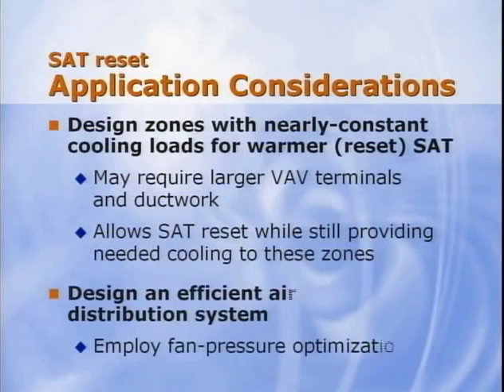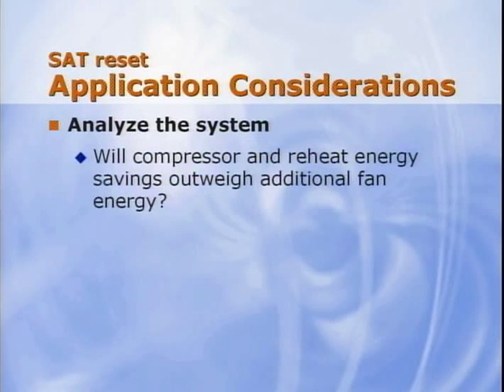Also, design the air distribution system for low pressure losses and use the fan pressure optimization strategy to minimize the penalty of increased fan energy when the supply air temperature is raised. When considering using supply air temperature reset in a rooftop VAV system, first, analyze the system to determine if the savings in compressor and reheat energy will outweigh the increase in fan energy.